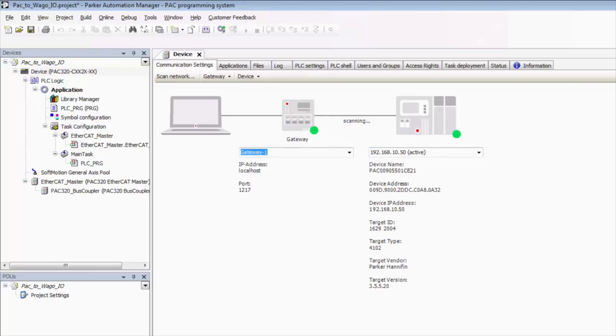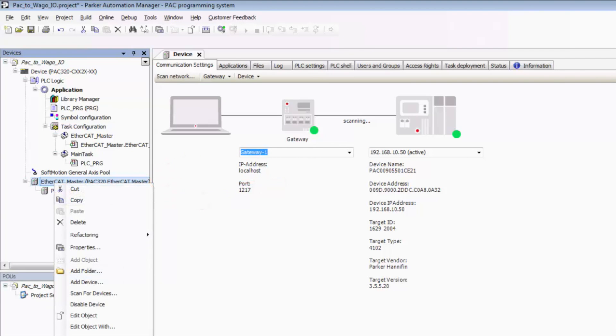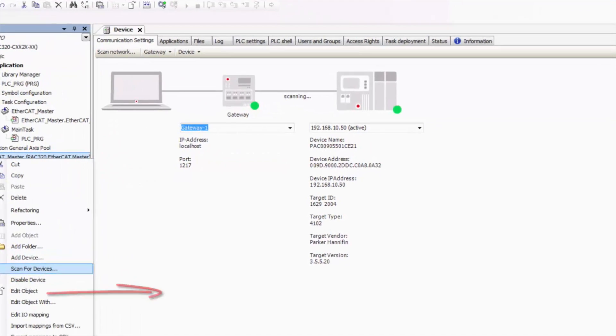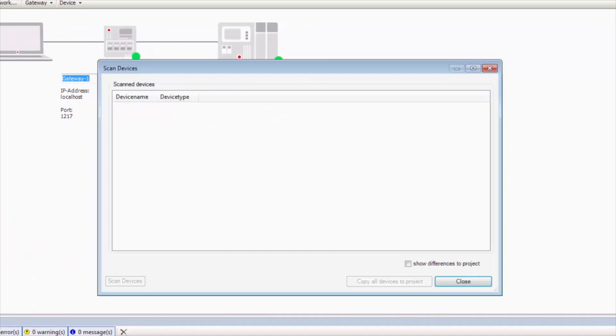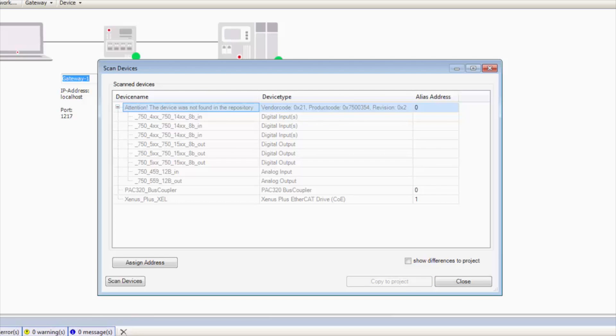From there we can go to EtherCAT master. We can right click and select scan for devices. This should automatically find all EtherCAT devices on the field bus. We see right here this device is not in our repository. That's actually our WAGO EtherCAT coupler.